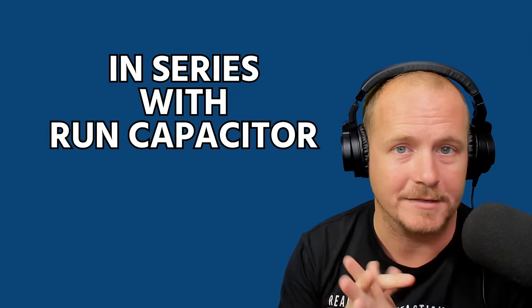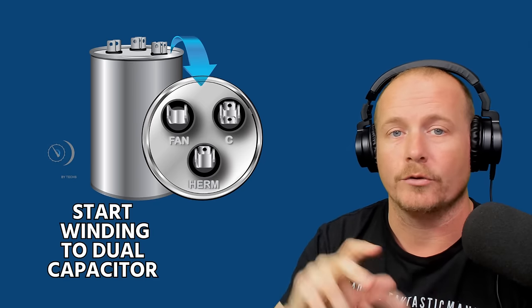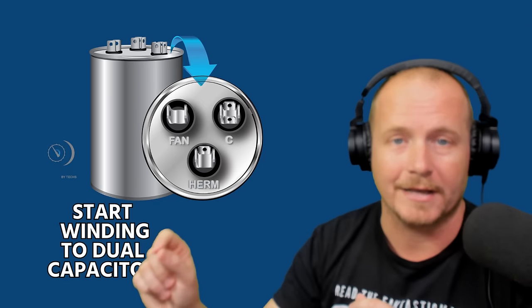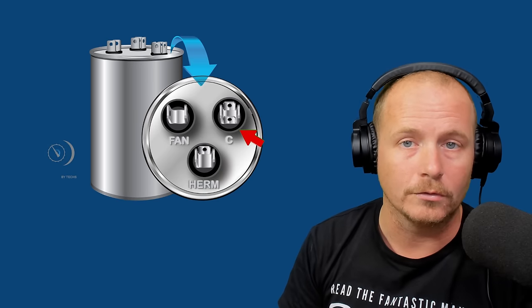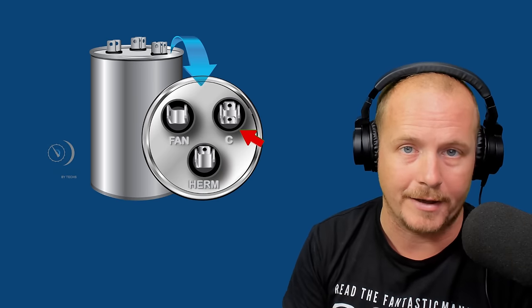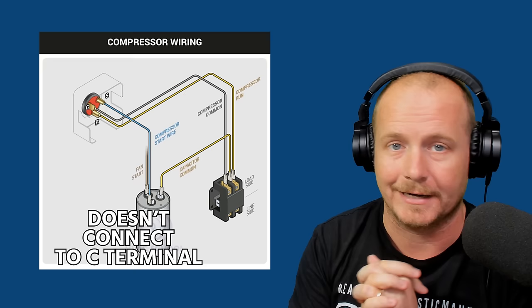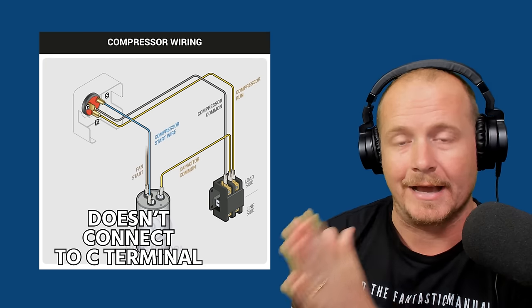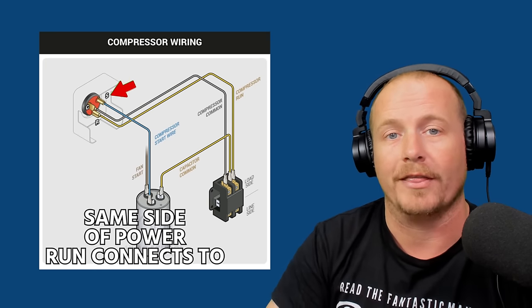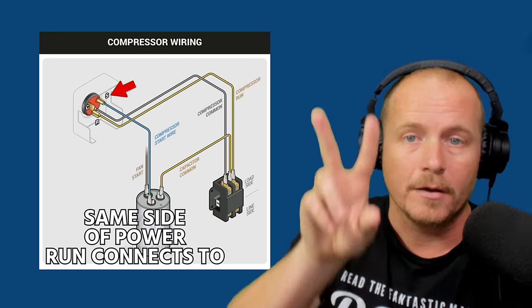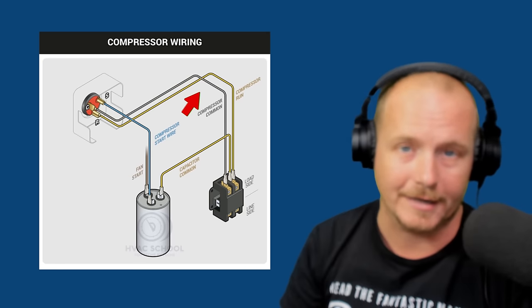Also, just a quick tip to keep in mind, when you connect your start winding to a dual capacitor, you're going to connect that to the HERM terminal, but the C terminal on a dual run capacitor, the typical run capacitors we see on a lot of units, that does not connect to the C terminal on the compressor. It connects to the same side of power that run connects to, because remember, common and run are the two that are connected to power.